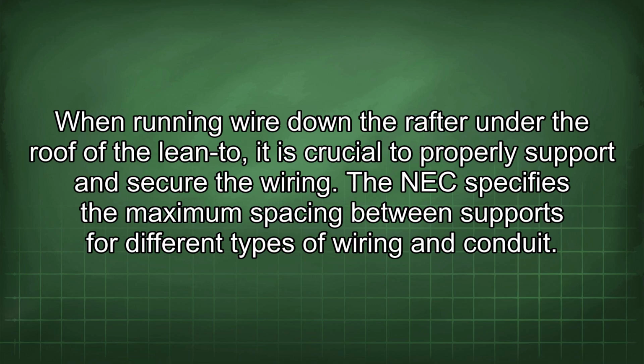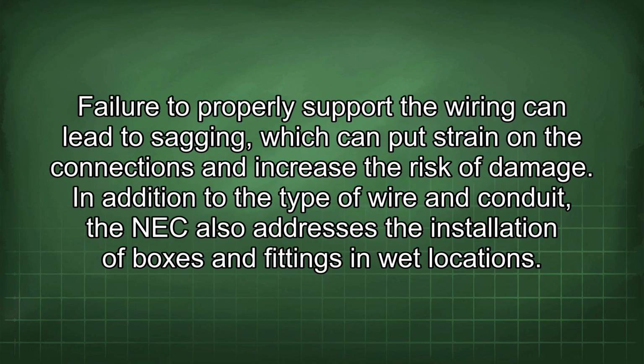When running wire down the rafter under the roof of the lean-to, it is crucial to properly support and secure the wiring. The NEC specifies the maximum spacing between supports for different types of wiring and conduit. Failure to properly support the wiring can lead to sagging, which can put strain on the connections and increase the risk of damage. In addition to the type of wire and conduit, the NEC also addresses the installation of boxes and fittings in wet locations.